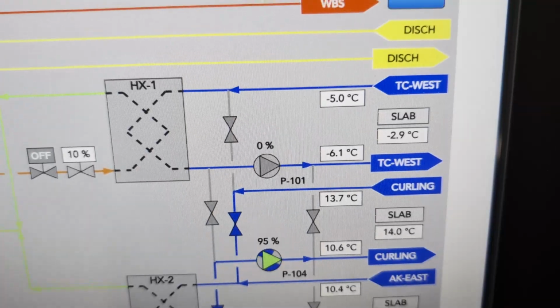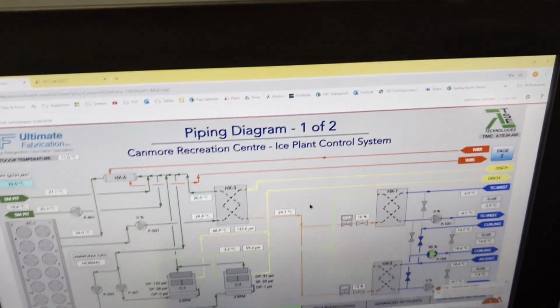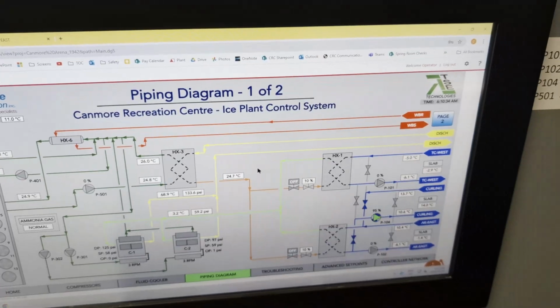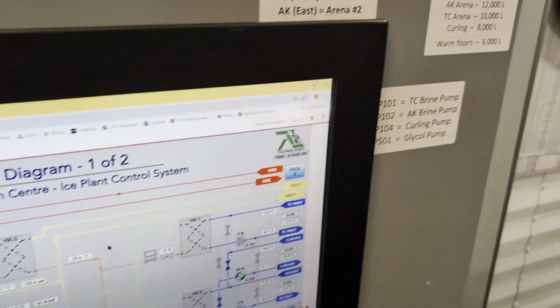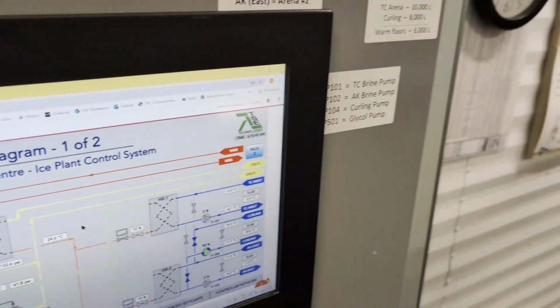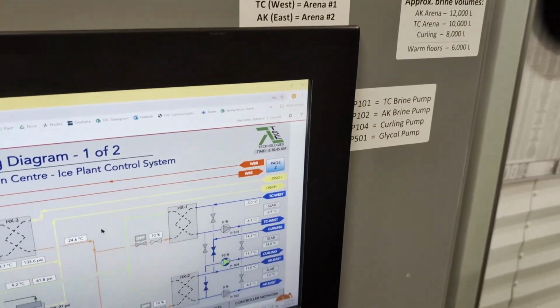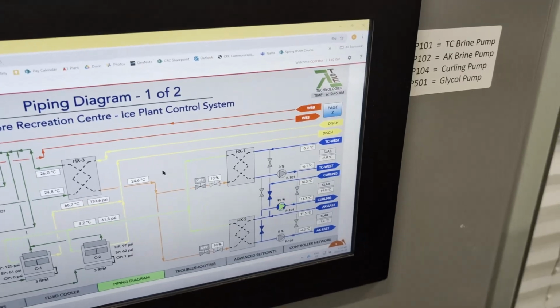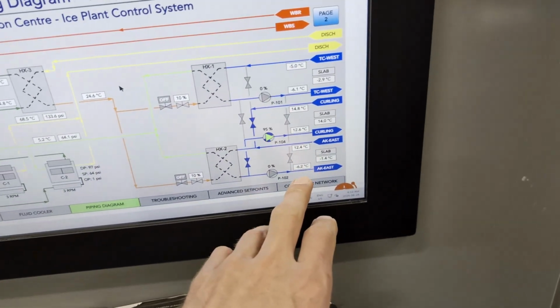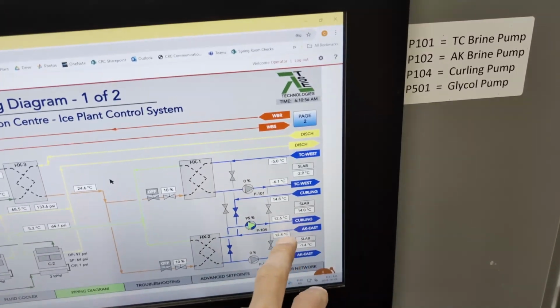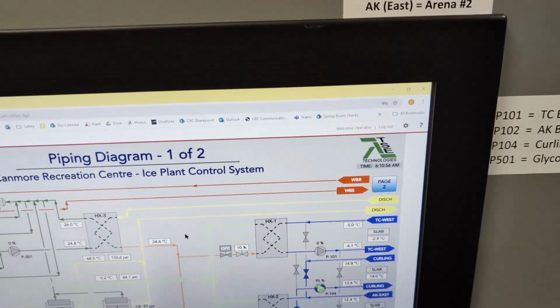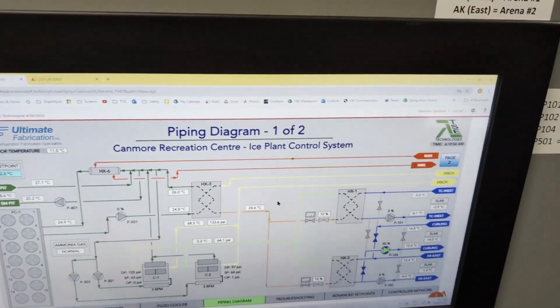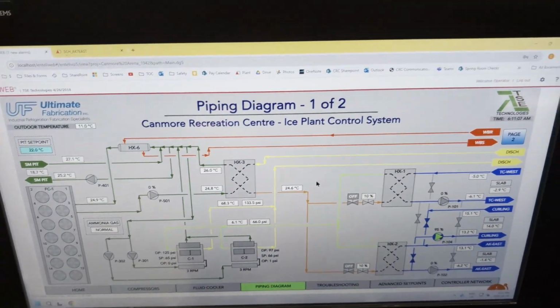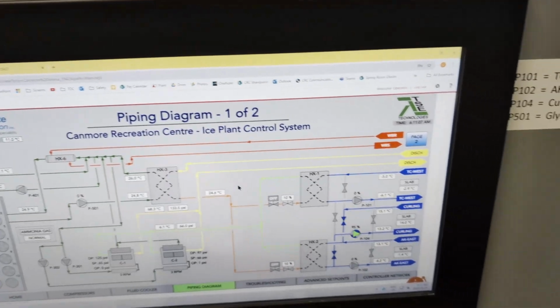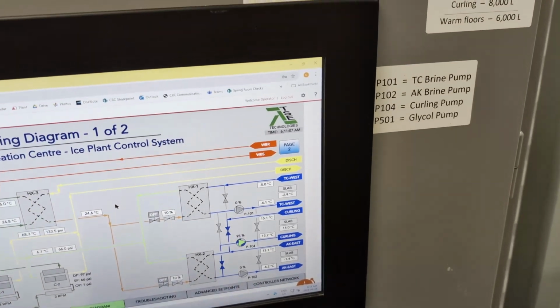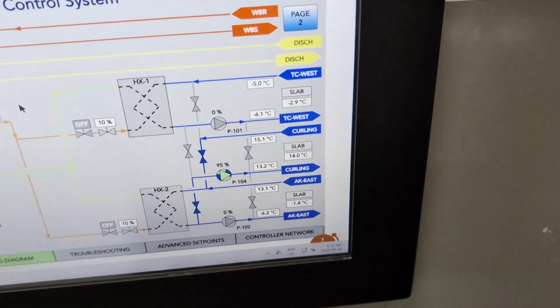And as the brine mixes and you get the temperature of the brine, eventually it'll equalize kind of. You'll still see once we start the AK pump that it's going to be going out warmer than it's coming back because the slab's going to cool the brine. But because we're on ice out for both these floors, the compressors are not going to run, and we're just going to basically use the pumps to circulate the brine and mix it.